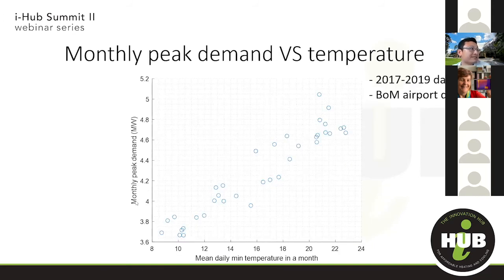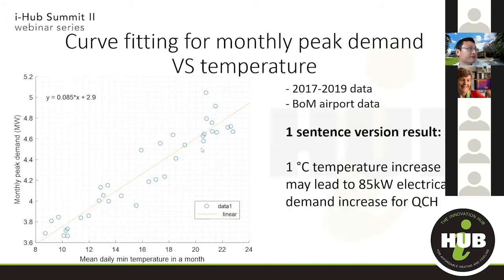If we plot the monthly peak demand data as a scatter plot again against the same mean daily minimum temperature in a month, we see a similar but slightly more scattered relationship. This is also 3 years of data, 2017 to 2019, with the Brisbane airport temperature data. If we do similar curve fitting or regression study, we find that a 1 degree Celsius temperature increase may lead to an 85 kilowatt electrical demand increase for the QCH precinct.